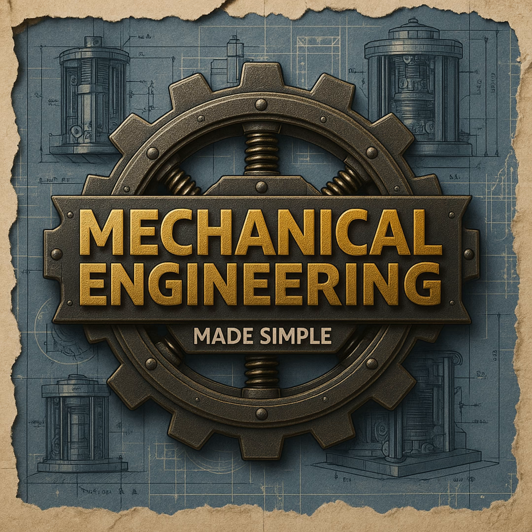Yikes. Okay, that makes the next one, the lobe compressor, sound appealing just for its simplicity, even though its compression method is, well, odd. It is definitely counterintuitive. Lobe compressors don't really compress the air inside the machine at all. They are clearance-type machines, meaning the rotors, which look like figure eights or lobes, just trap air and push it towards the discharge port. The actual compression only happens when that air hits the back pressure already existing in the discharge pipe system.